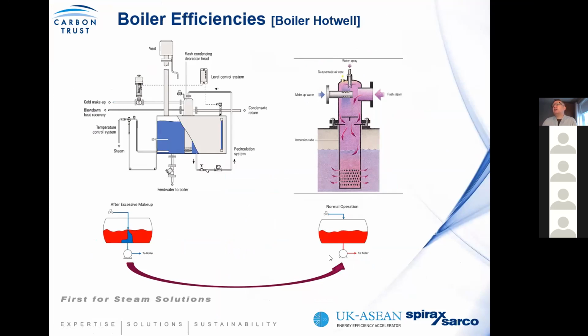So when you start looking at your non-deaerators, what you should also look at is that if you have what we call a hot well tank, you should also have what we call the atmospheric deaerator head installed. And the idea here is that you would take your makeup water and your condensate recovery, and through this immersion, you would basically blend the two streams into each other, such that again, you're creating the isothermal water temperature and you don't have the impact of the cold dumping. If you have a hot well tank where you have cold water coming in one side and condensate on the other side, there's a potential for thermal stratification. And again, you could find significant temperature swings to your boiler water.